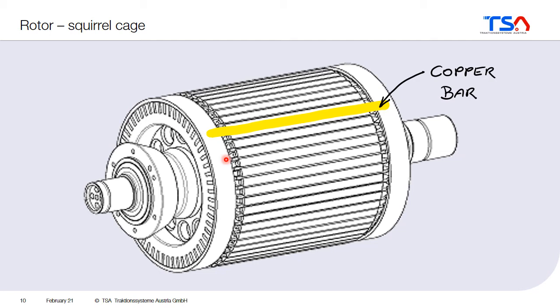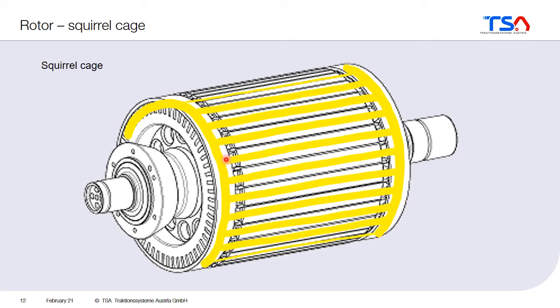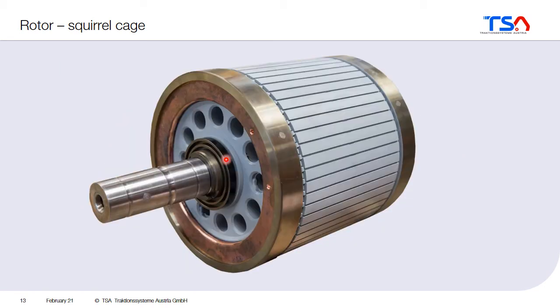Let's have a look now at the rotor and how it is built. Inside the rotor slots of the rotor lamination there are copper bars. At the end, all the copper bars are connected by short circuit rings. So there are the copper bars and the short circuit rings, and together they form the squirrel cage. This is the complete structure of the rotor of an induction machine — it is quite simple, and that is why it is also so successful.